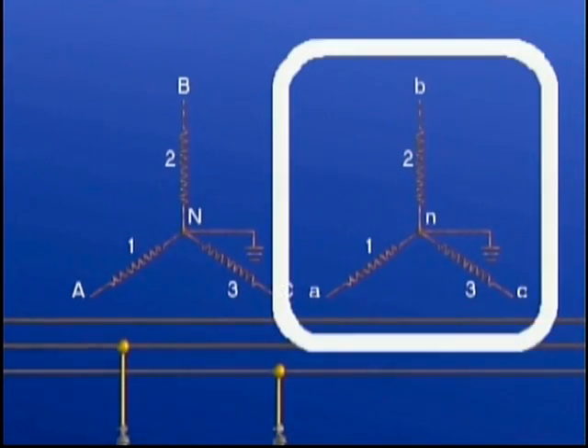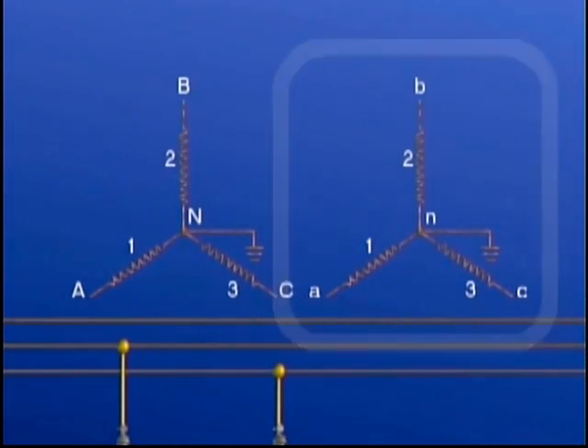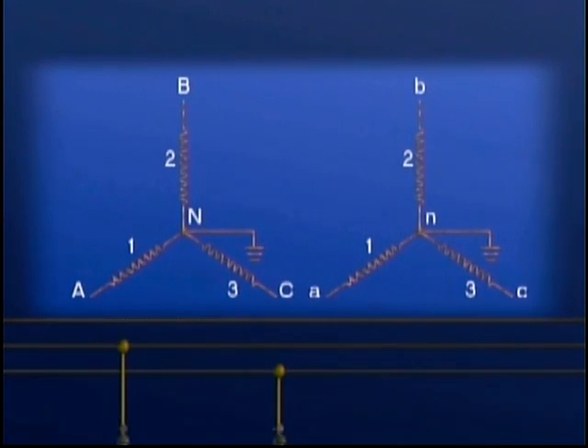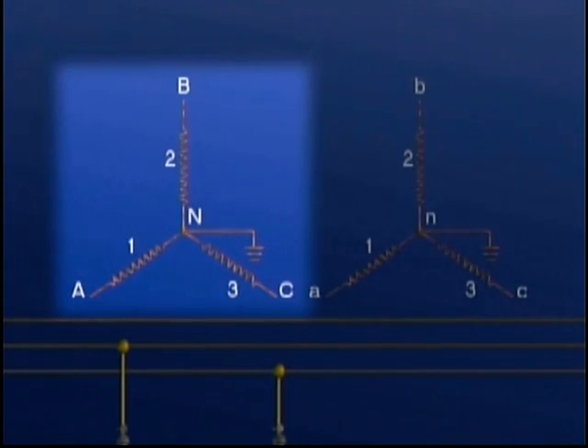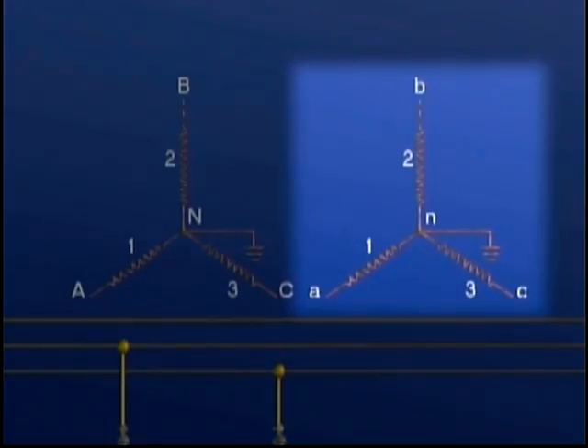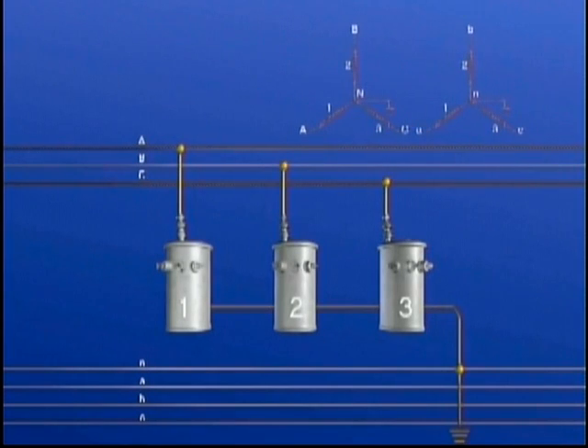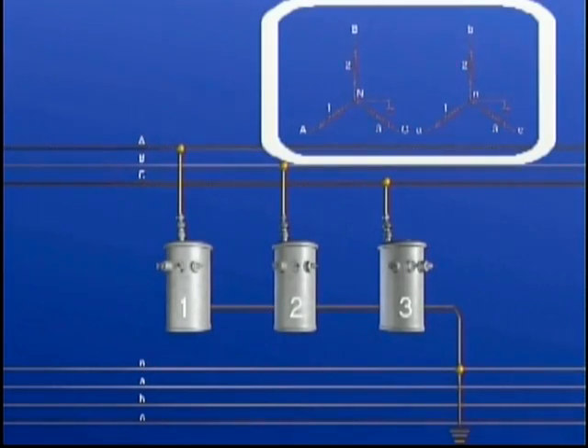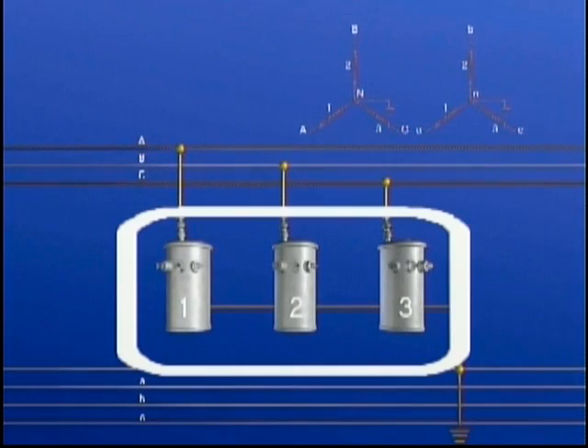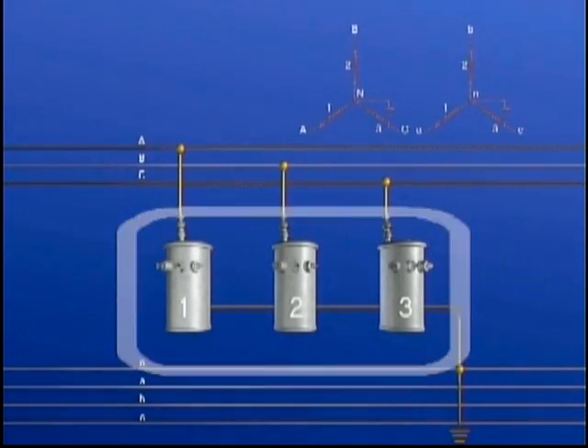This phasor diagram illustrates the Y connection we're going to make on the secondary side of the 3-phase bank. Notice that the phasor diagrams that illustrate the Y connection are arranged identically. The uppercase letters on this phasor diagram refer to the primary connections and the grounded system neutral. The lowercase letters on this secondary phasor diagram illustrate the secondary connections and the grounded system neutral. Again, as an aid to explaining this connection, we've numbered the windings on the phasor diagrams that correspond to the transformers 1, 2, and 3.